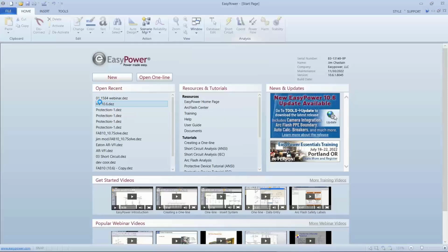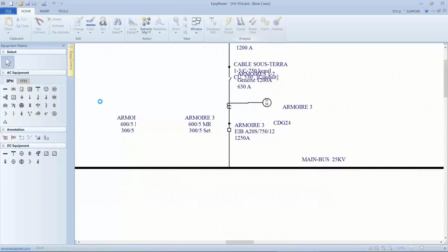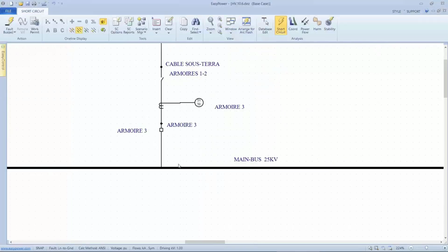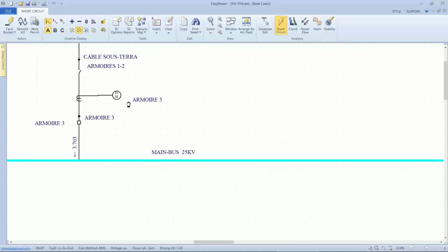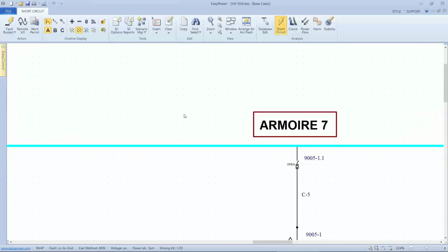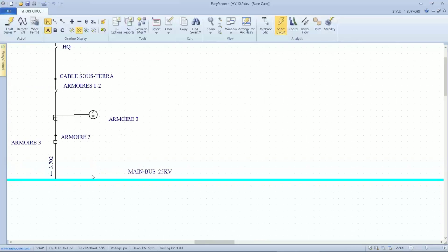I had someone come in saying, Jim, I've got my relay set up for 1800 amps. I'm seeing 4,000 amps on a fault current. Why isn't it tripping? So I saved this, or it got saved with my fuse open. Okay, let's go back and try this again.